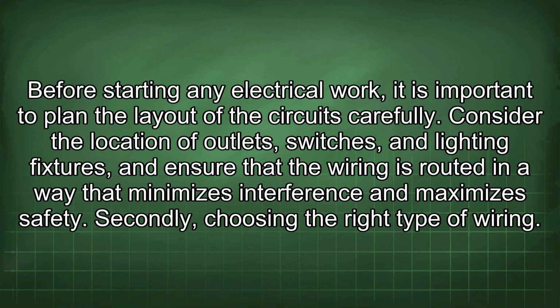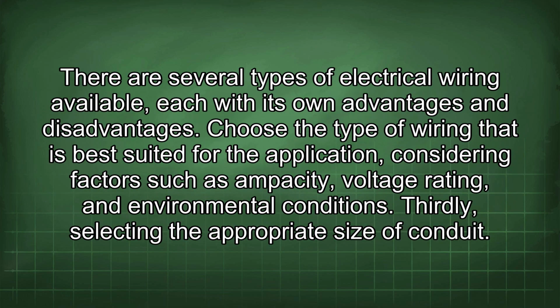Consider the location of outlets, switches, and lighting fixtures, and ensure that the wiring is routed in a way that minimizes interference and maximizes safety. Secondly, choosing the right type of wiring. There are several types of electrical wiring available, each with its own advantages and disadvantages. Choose the type of wiring that is best suited for the application, considering factors such as ampacity, voltage rating, and environmental conditions. Thirdly, selecting the appropriate size of conduit.